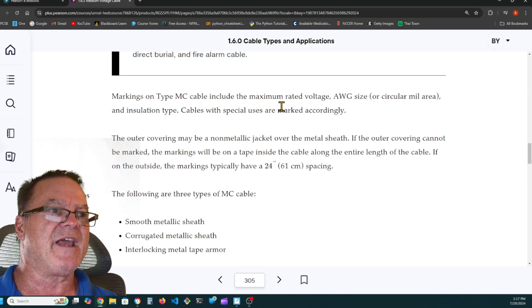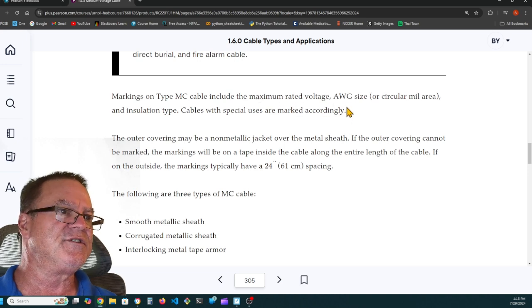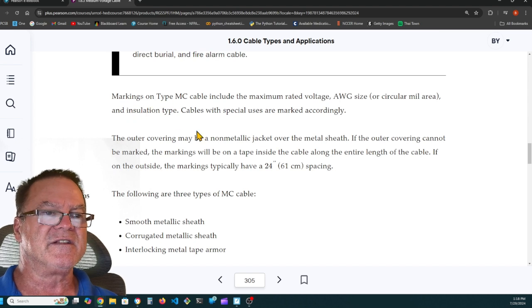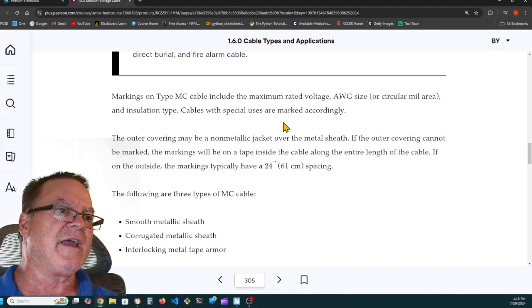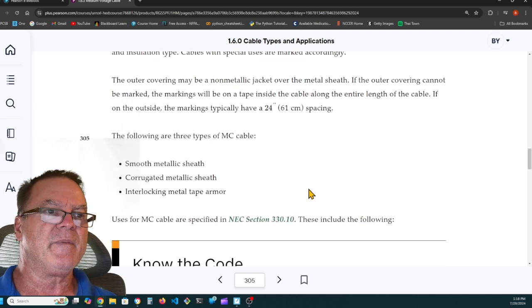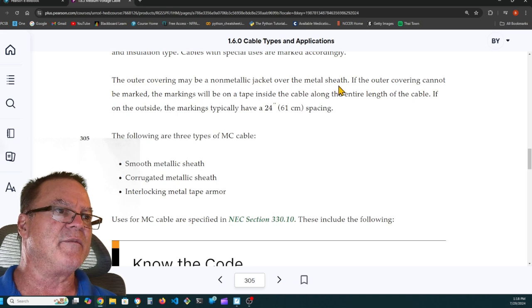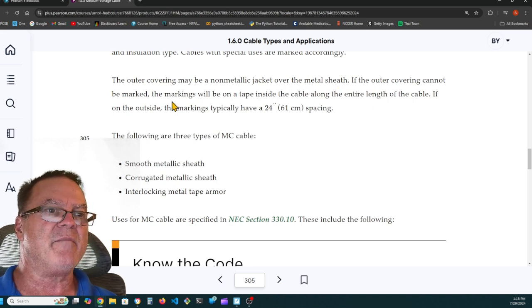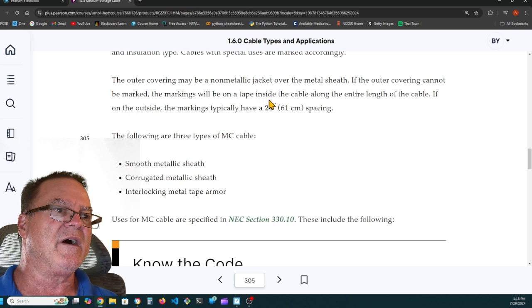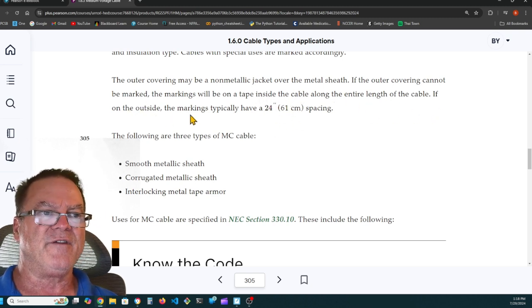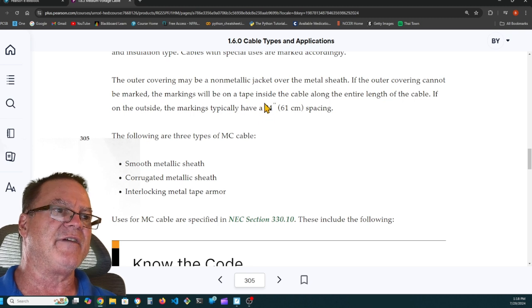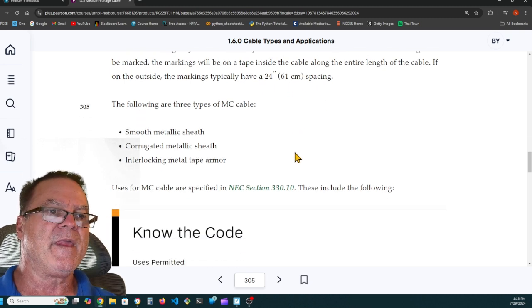Markings on type MC cable include the maximum rated voltage, gauge size or circular mil area, and the insulation type. Cables with special uses are marked accordingly. The outer covering may be of non-metallic jacket over the metal sheath. If the outer covering cannot be marked, the marking will be on a tape inside the cable along the entire length of the cable. If on the outside, the markings typically have a 24-inch spacing.